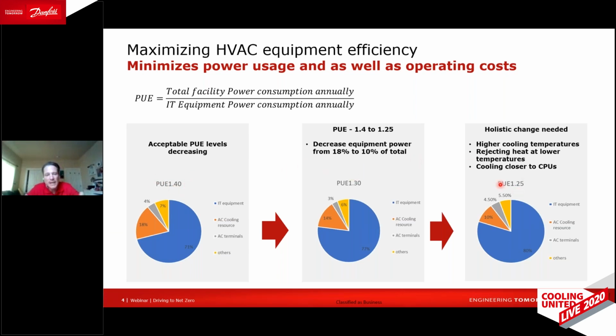But the critical side note is the air-cooled cooling resource. As you see the power usage efficiency decrease in that progression, you see a corresponding decrease in energy usage specifically for the cooling equipment, which means higher efficiency, tied to the trends I mentioned earlier and will detail more later.